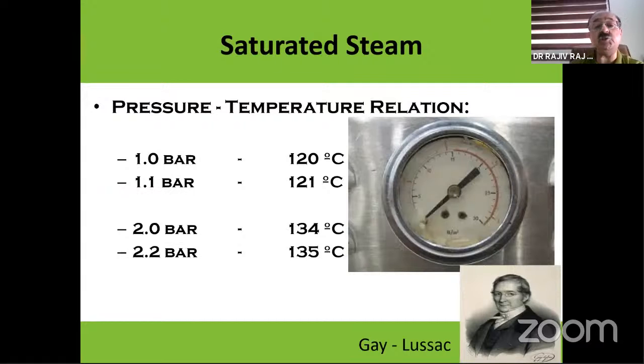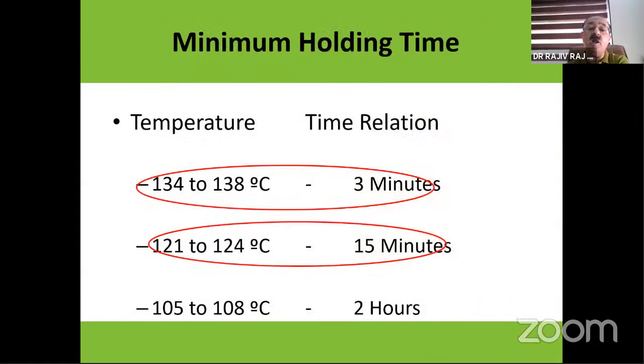And if we have a pressure of 1 bar, then the water will boil at 120 degrees. And if we can increase it to 2 bars, then the water would boil at 134 degrees, giving rise to saturated steam. Now, if we are holding the equipment for 3 minutes at 134 degrees, all spores die. And if we are having a temperature of 124 degrees for 15 minutes, that gives us the amount of time that we have to hold at a particular temperature.